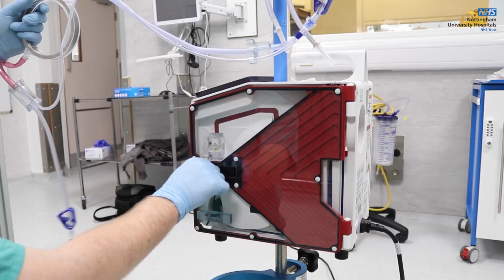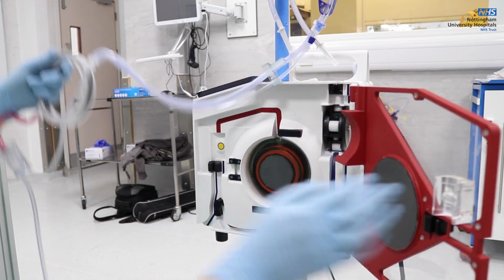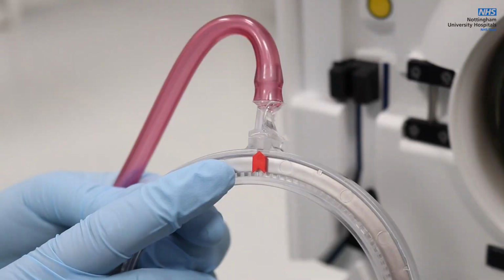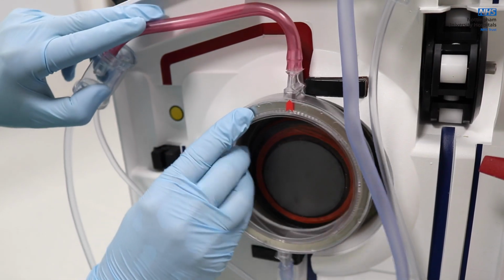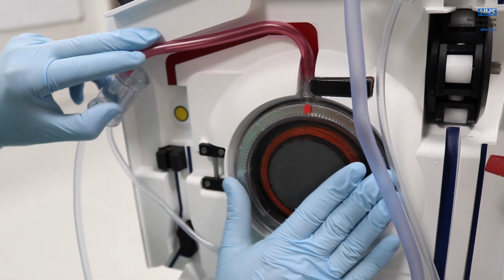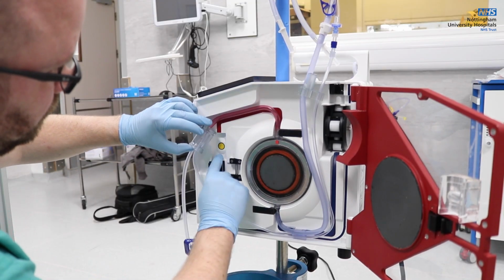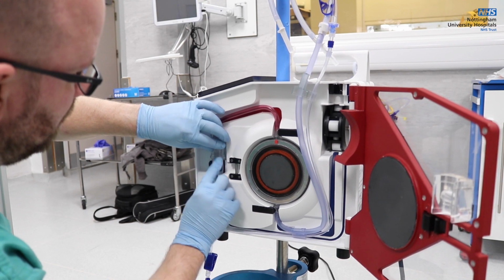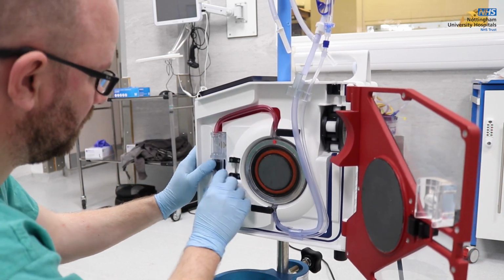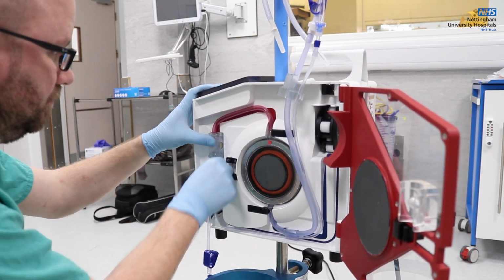Open the door of the unit and load the circular heat exchanger with red arrow pointing up and the red tubing aligned with the red line on the system. Align the red tubing on top of the red stripe and place the pressure chamber into the pressure channel. Press the infused line into the secondary air detector. Please note, the infused line should be within the air detector.